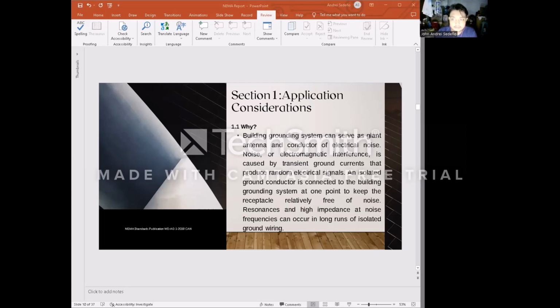This application guide covers wiring devices and accessories intended to help protect sensitive equipment from malfunction due to noise on the equipment ground path. Devices include receptacles, single or duplex, with straight blade or locking NEMA configuration, rated 15 amperes to 60 amperes and 125 volts, single or duplex with straight blade or color coded mating plugs, and wall plates to identify isolated ground receptacles.